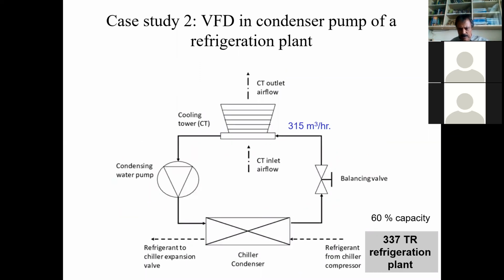So you may have a refrigeration plant, 337 TR. From the refrigeration plant, the refrigerant is coming out, going into the condenser. The refrigerant condenses. What happens to the cooling water? The cooling water comes here in this direction and then goes into the cooling tower. 315 meter cube per hour is the flow rate. So 25 degrees and 27.7. So this is the outlet actually.